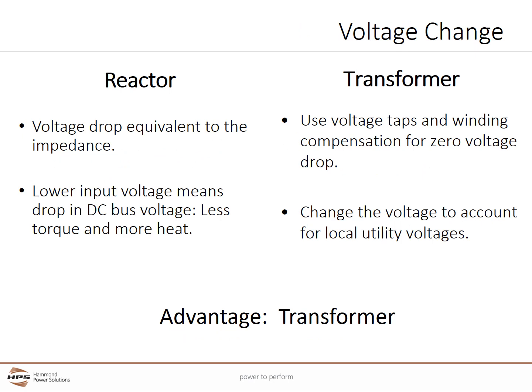Voltages can change. With line reactors, there is always a voltage drop equivalent to the percent impedance at full load. Lower output voltages can mean lower voltages getting to both the VFD and the motor, which means less motor torque, higher currents, and more heat. Transformers can use their winding ratio to adjust voltages as needed. Taps can be used to adjust for localized low voltage conditions. There is no voltage drop with the transformer. Output voltages can be changed as needed. This gives the transformer the advantage.